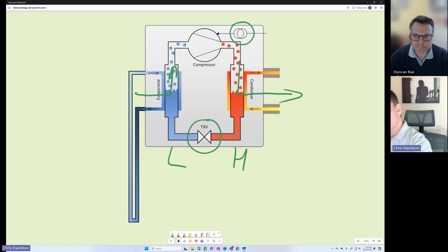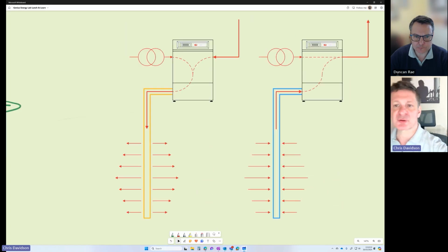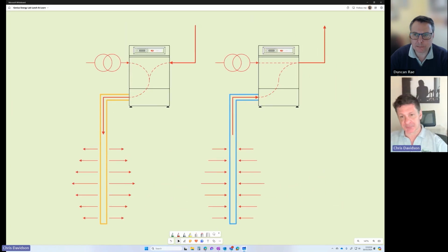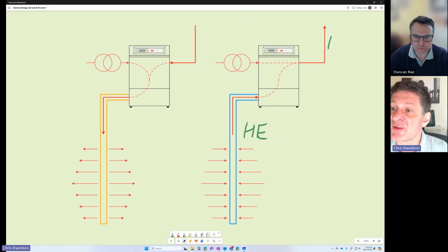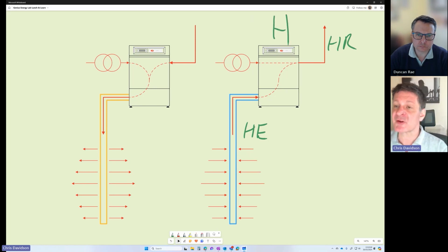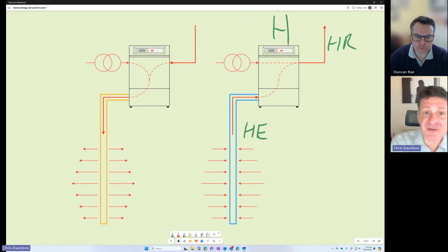So how does that apply to ground source design specifically? Let's start with some terminology. The heat we take from the ground we call the heat of extraction, and the heat we put into the building is called the heat of rejection. On this side we're heating, taking heat from the ground and putting it into the building. On this side we're cooling, taking heat back from the building and putting it into the ground.